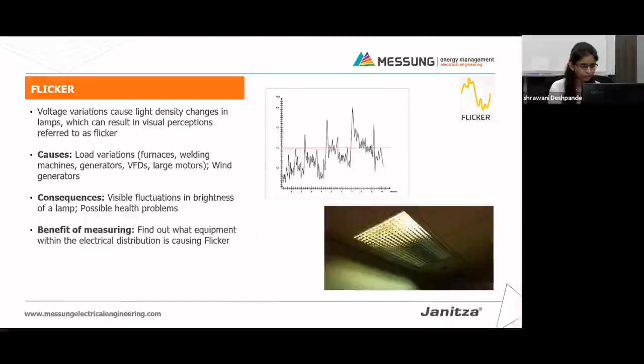This can be caused by load variations such as furnaces, welding machines, or generators, or it can even be due to faulty LED drivers. As we all know, LED lighting is becoming more and more popular, and we are replacing our old systems with LED lighting systems, but a faulty driver can also cause flickering of light. Then we have one standard, IEC 61000-4-15, which defines flicker, and it also defines the artificial units such as Pst, which is short time flicker, and Plt, which is long time flicker. So a benefit of measuring is that we can find out which equipment in the electrical distribution is causing flicker.